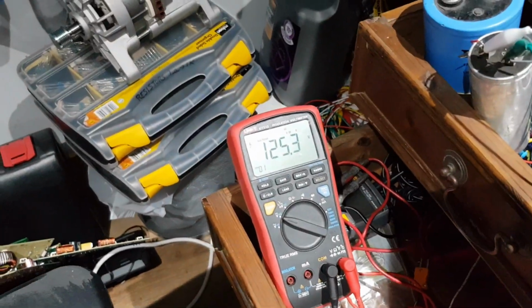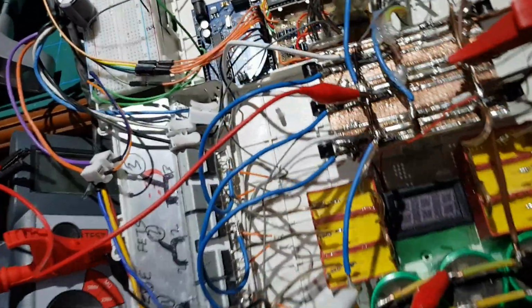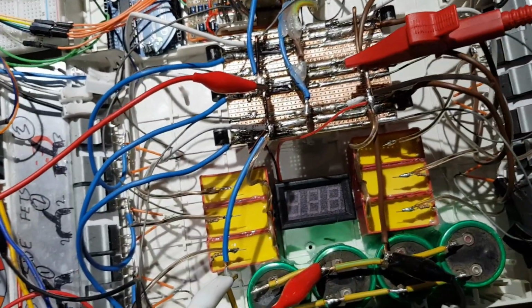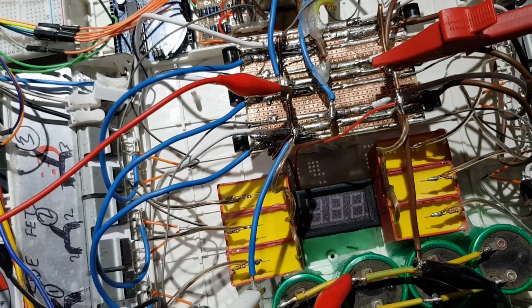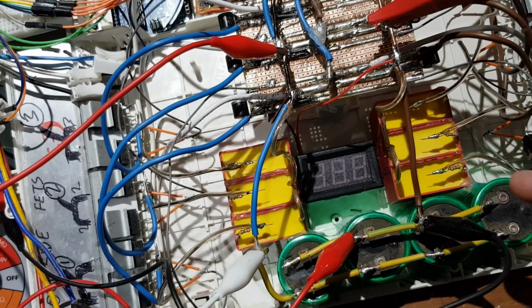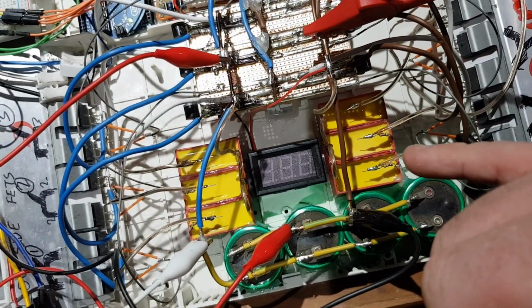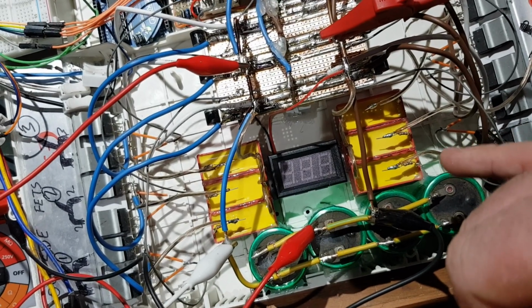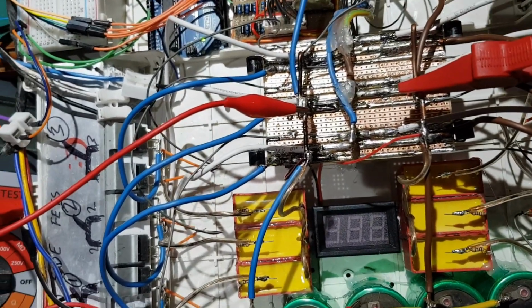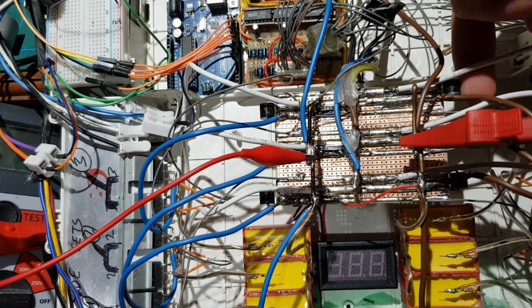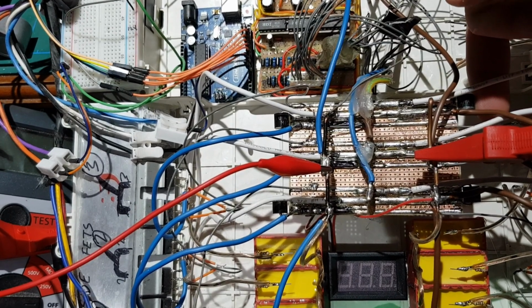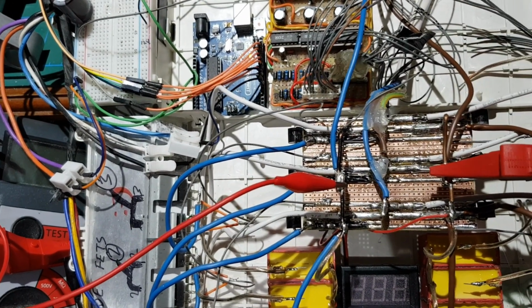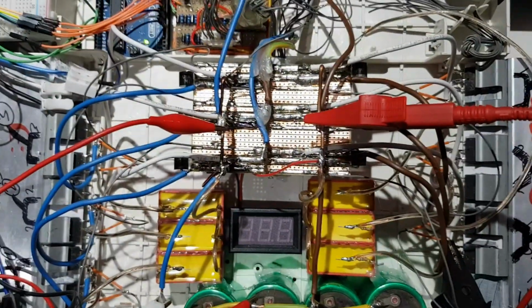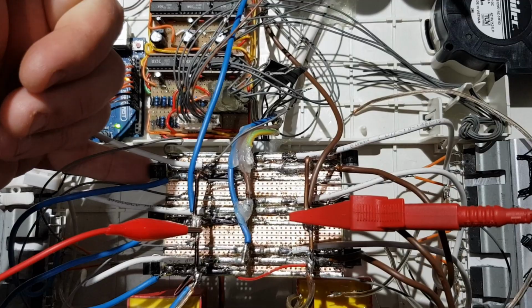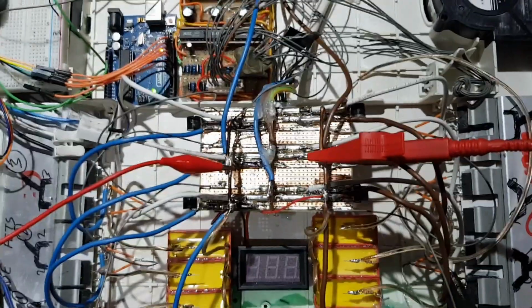What it's a good idea to do, when you're doing your final test, is have a good sniff around for burning, because when you turn that voltage up, all sorts of things can happen, like your snubber capacitors will suddenly get boiling hot, because they're dealing with so much current. And by the way, don't touch your buses unless you exactly know what you're doing. Your diodes might start getting hot, your phase rectification diodes. Do you know what? It's all stone cold, which is good.